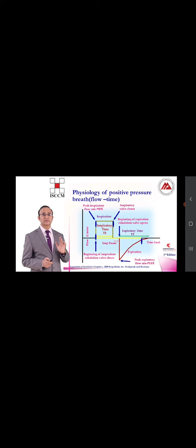Now, when a mechanical breath is delivered, or when the flow starts, it produces changes in the pressure, volume and flow in the respiratory system, and these are directly dependent on the mechanics of the respiratory system. So when you deliver a mechanical breath, pressure, volume and flow can change. But at any given point, you can control one of them; the other two will be dependent on the airway resistance and the compliance of lung and chest wall.